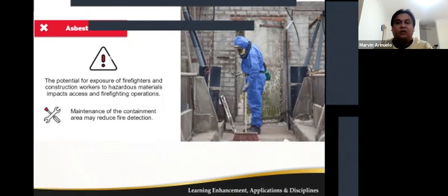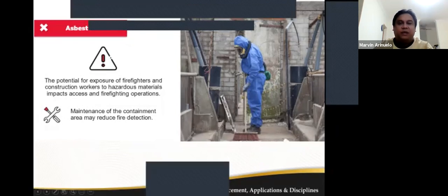The maintenance of the containment area may reduce fire detection and will lengthen the amount of time before manual fire suppression by workers outside the containment area is possible. The widespread use of tarps and plastic film may also contribute to the fire load and fire spread.